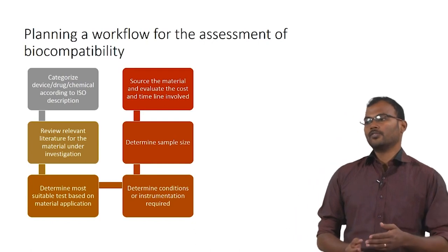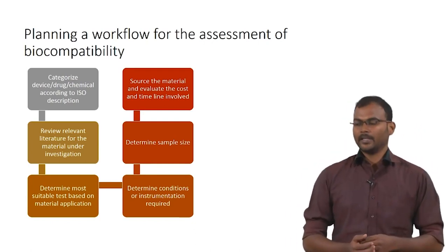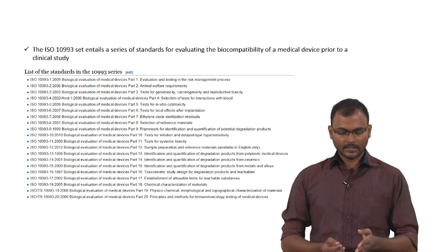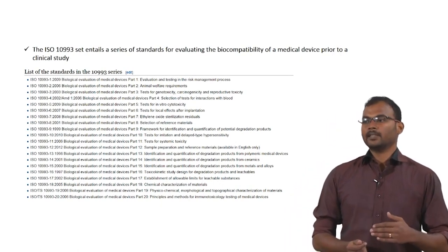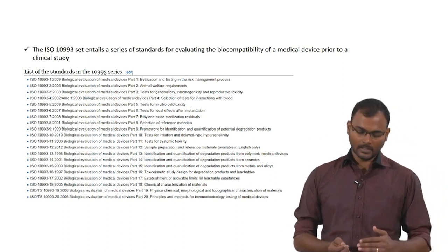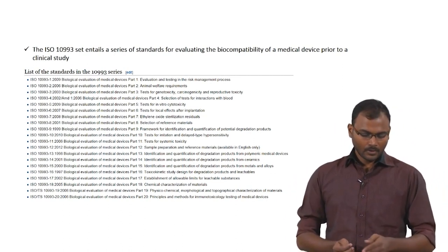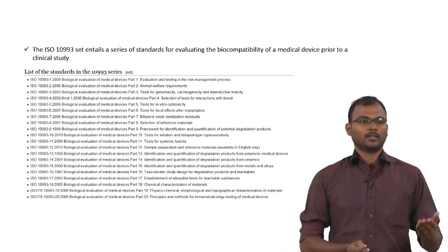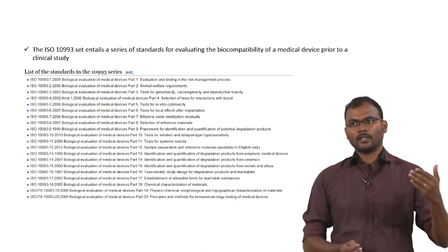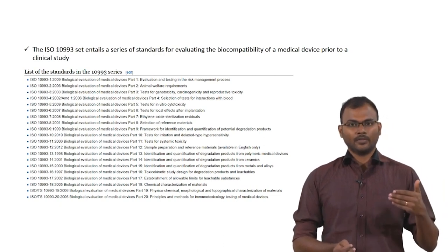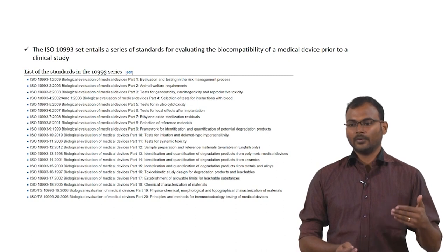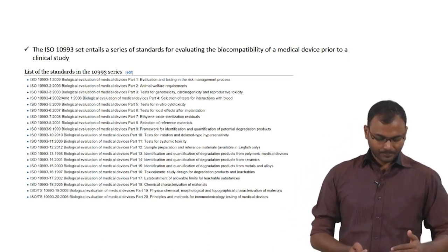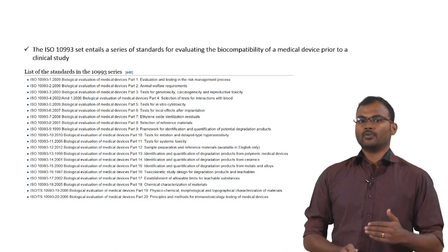Then finally you have to consider the cost and time involved in developing that material. These are the standards given by ISO. Each of the standards has a different set of guidelines for different applications, such as 10993-5, which only involves in vitro cytotoxicity. Whatever toxicity experiments I have mentioned, it will give you clear guidelines on how to do it if your material is a flat surface, and how to do it if your material is a scaffold or hydrogel.